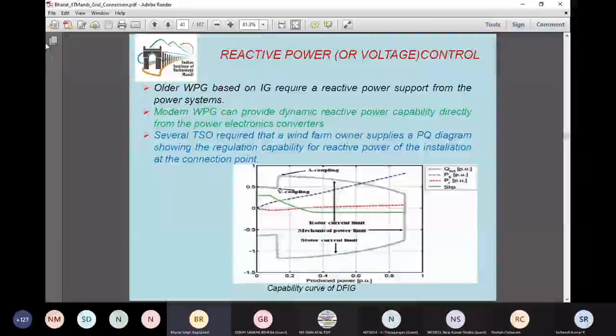That is why such a curve is there, and it is expected by the transmission system operator, so that an operating point can be found, as well as how much margin there is by which reactive power can be injected into or absorbed from the grid. Here you can see the green line is given as the slip speed. This slip speed is based on the maximum power point tracking algorithm and the availability of wind speed. It is followed by most variable speed wind energy conversion systems, and this overall capability curve is obtained for this given slip speed. Fine. So next slide, please.